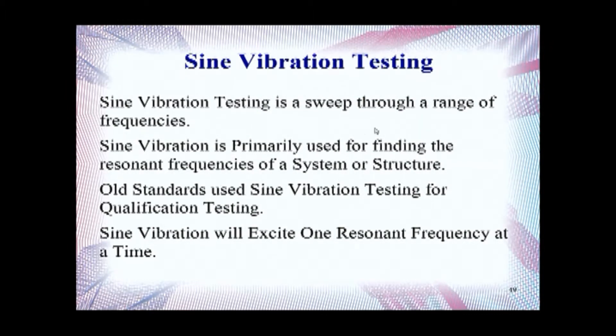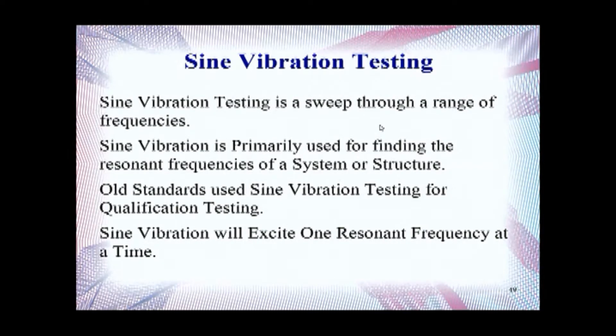What is Sine Vibration Testing? Sine Vibration Testing is a sweep through a range of frequencies. The test sweeps through one frequency point at a time in the upward direction to the maximum frequency for the test profile, or it can also sweep downward from the highest frequency to the lowest frequency in the test profile, one frequency point at a time.